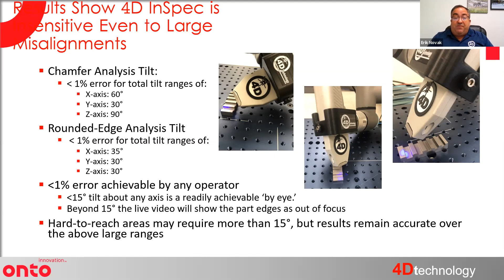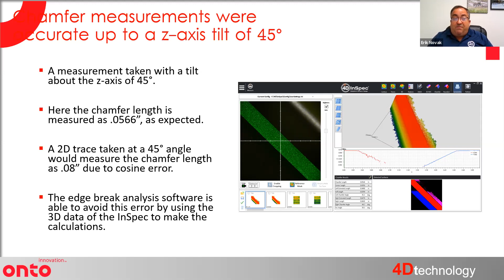So here's just an example of a measurement where a feature is canted at 45 degrees with respect to the field of view. And we're able to measure, the chamfer length was designed to be 0.0566, and that's actually what it was measured despite being off by a huge angle. Whereas a 2D trace there would actually measure that, if you looked at an X trace or a Y trace, as 0.08 inches. So off by more than 25%.